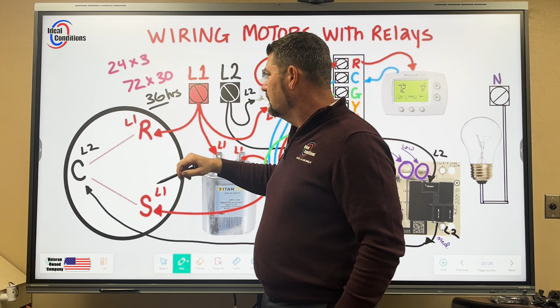That your evaporator coil was either warm, if it was a winter time, or it was cold in the summertime for cool mode. You had the amp draw of just the fan motor, transferring heat still and humidity out of the air for 36 hours in a month without a compressor running. So you have to understand that that off delay is important. And now you can get rid of it. We'll talk about that. But it's very important, because 36 hours, I can't say it's free air conditioning, because it's not free to run a blower motor.